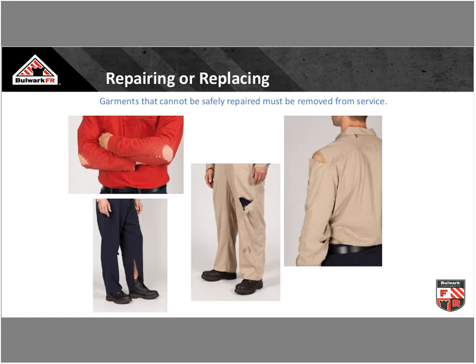Repairing or replacing, this is always tricky because there's no hard and fast guidelines for repairing and replacing FR clothing. When they ask us as manufacturers what we recommend, our rule of thumb is 3 inches and a nickel. If the hole is bigger than a nickel, don't fix it, replace it. If the tear is longer than 3 inches and not on a seam, replace it, don't repair it.